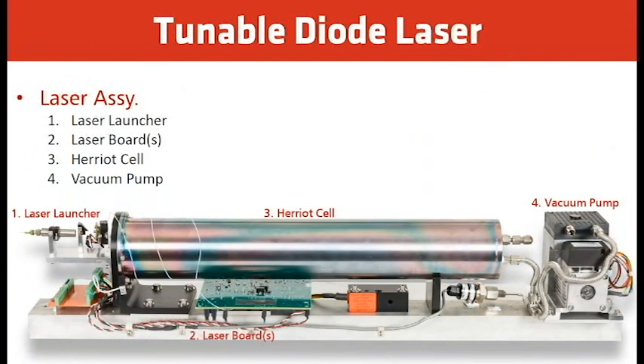On the left side here, what you see is the laser launcher, the cell window, and the detector. Underneath the cell, the Herriott cell here, you see different parts: the laser source, the heater, the pressure transducer, as well as the vacuum pump. Now, in order to make the measurement in our laser, the specific wavelength of the light emitted by the laser is controlled by adjusting the current as well as the temperature of the laser emitter. So the light goes through the laser launcher, gets focused on the laser launcher side, and then passes through the cell window and all the way through this Herriott cell.